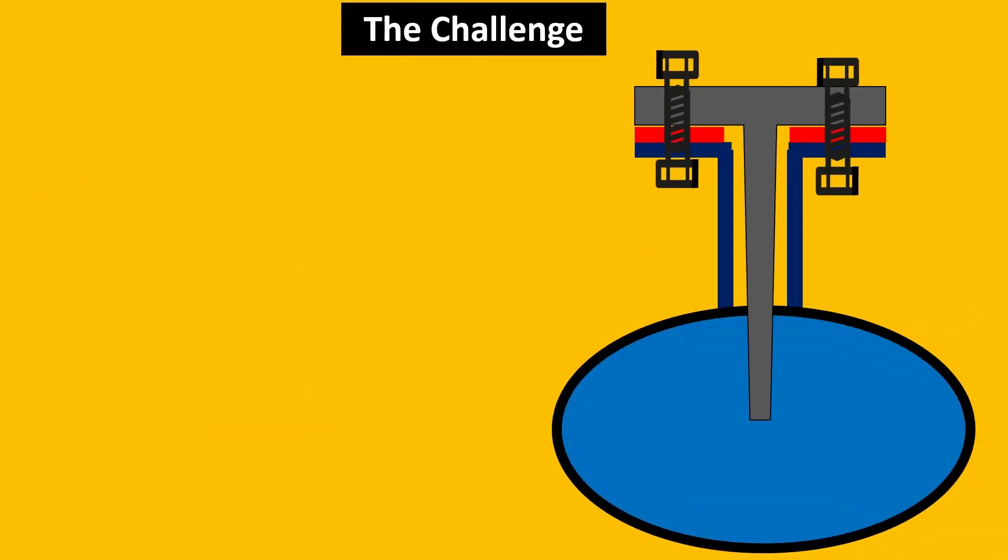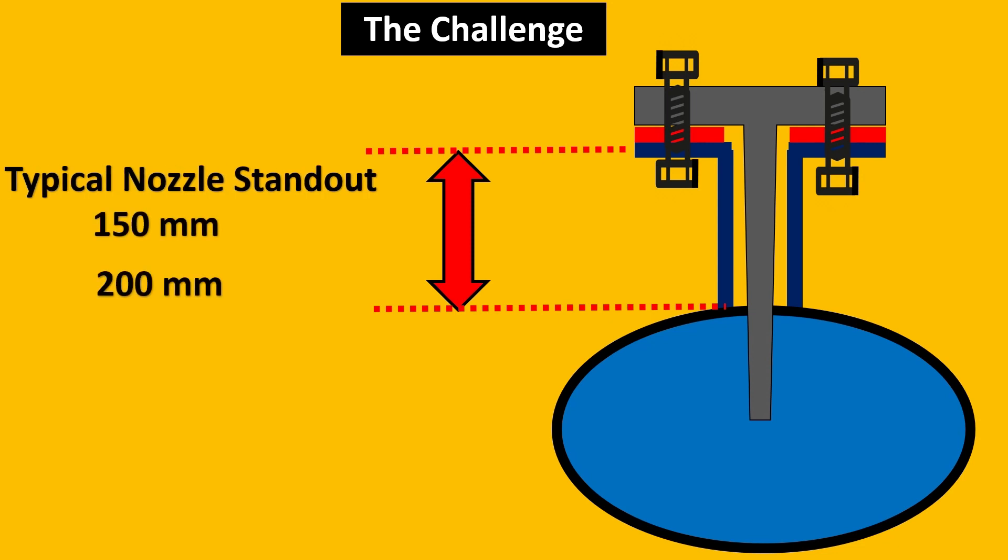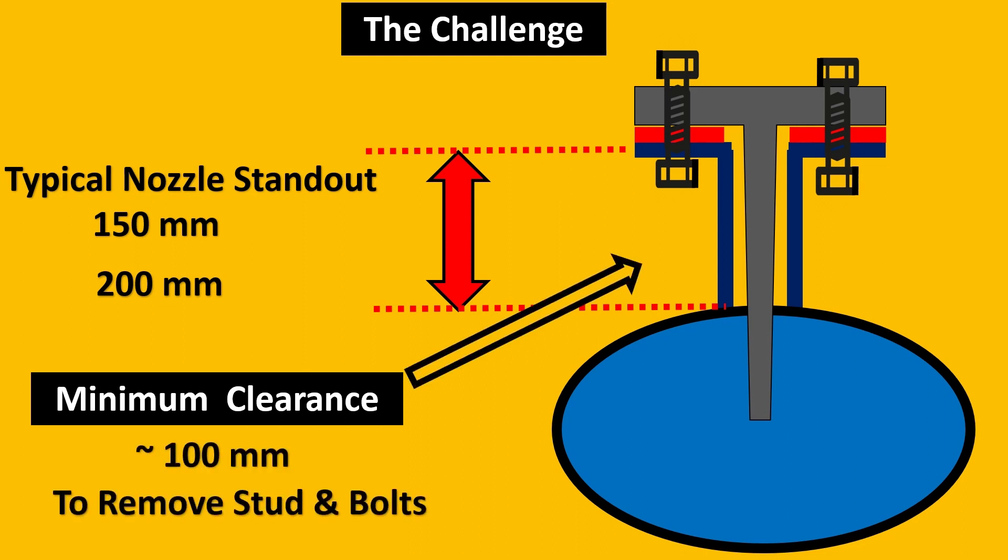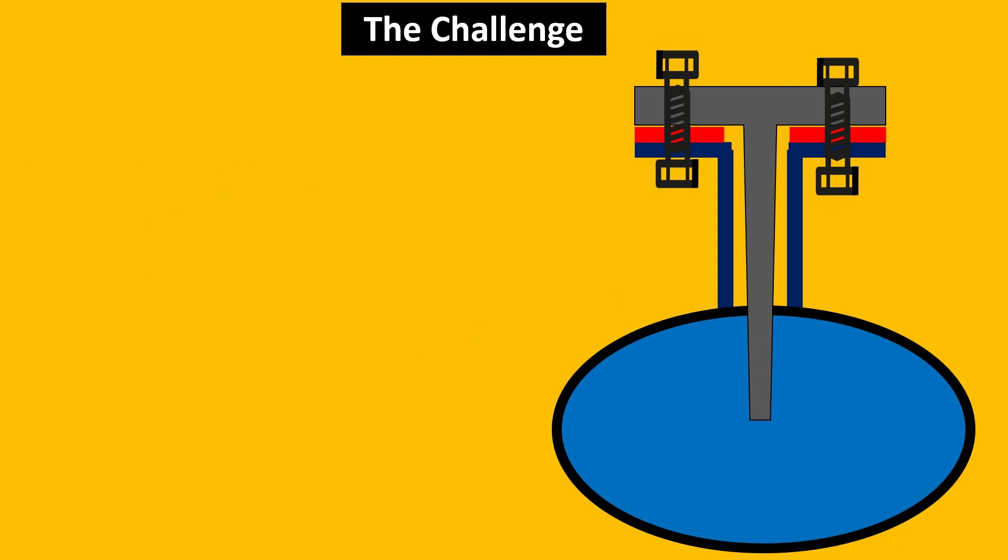So imagine the challenge here is that the nozzle standout which is typically around 150 mm or 200 mm in usual projects. And in these standouts we need a minimum clearance for the thermowells to be removed properly, from removing the bolts, studs, etc. So this clearance space should be around 100 mm. But if you see even if it is 150 mm we are getting more than 100 mm clearance space. So then what is the challenge here?